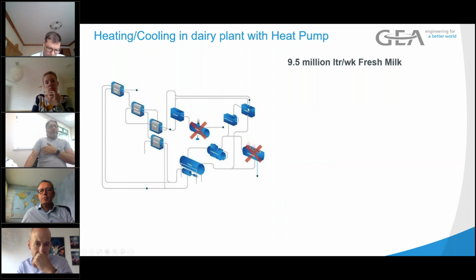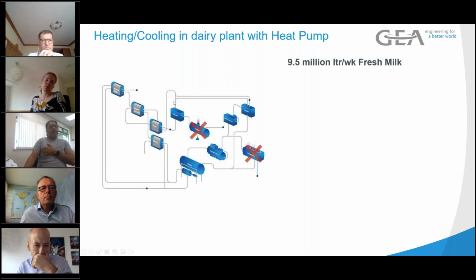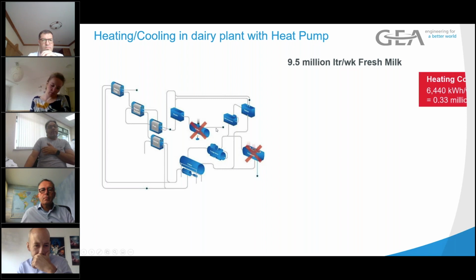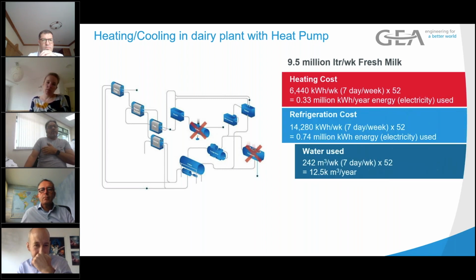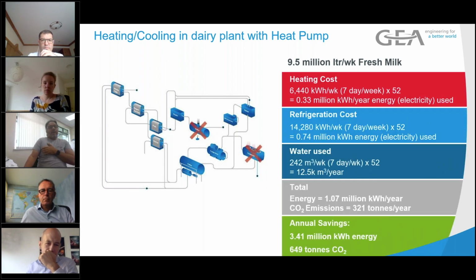Here we added a booster heat pump, so basically recompressing the gas up to 82 degrees, making an 82-degree water loop, and just sticking a 3-way valve in to blend it into the pasteurization loop. The reduction, again, 3.4 million kilowatt hours per year and 650 tons of CO2.